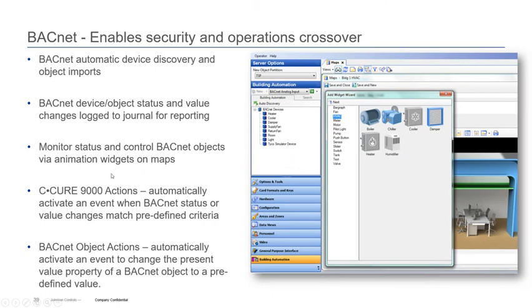So as far as what's coming into C•CURE, you can see the screen here. You can see boilers, chillers, status, coolers, whatever information can be discovered and mapped into C•CURE from a BACnet device can be shown. So you can look at the values, look at statuses. You can send actions back from C•CURE into a BACnet system to turn things on or off. And there are events you can trigger to change present value properties, for example, of a BACnet object. So again, this is more for C•CURE controlling the BMS functions, even maybe a subset of the overall functions. We do that by an automatic discovery method, and once they're discovered, you pick the points that you want to have exposed in C•CURE.